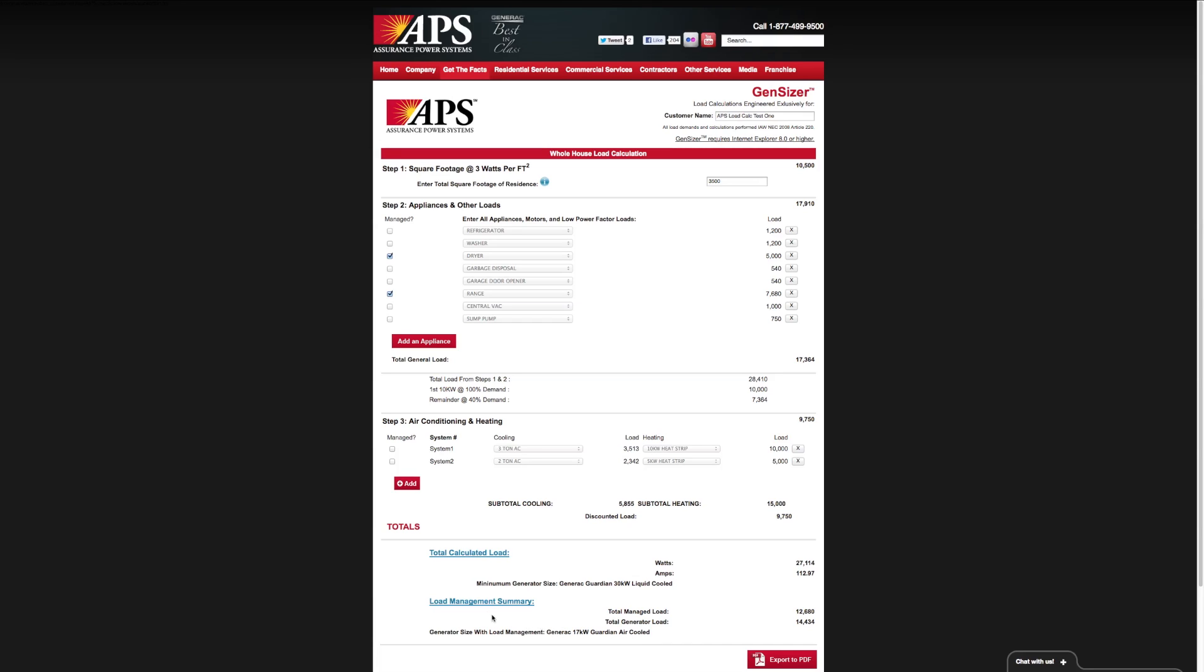Now that we're looking at the air cool, we're also going to probably need to manage one of these AC zones for motor load reasons. That's something you need to talk to an Assurance Power Systems design professional to make sure you're taking into account those motor loads. I'm going to select one of these AC systems. You can see that the total generator load is now minimized. Again, we may need to increase the size of this generator to account for the motor load capacity and starting requirements of this AC system.